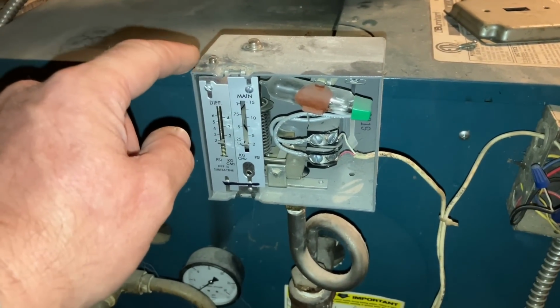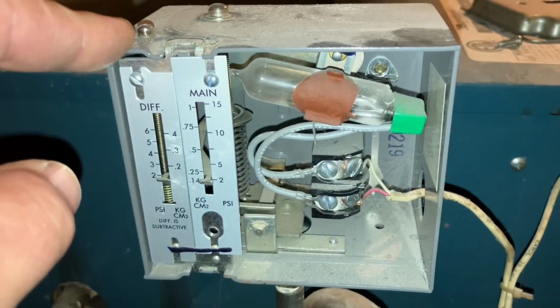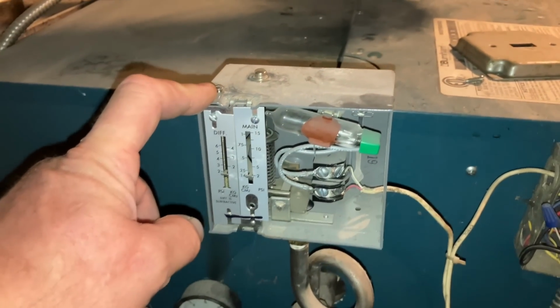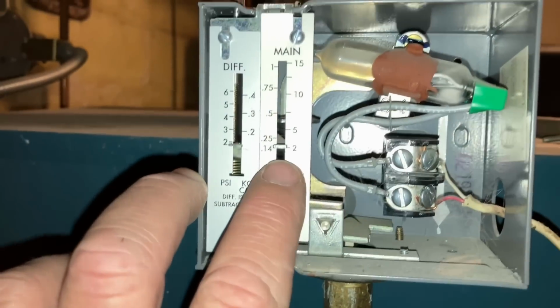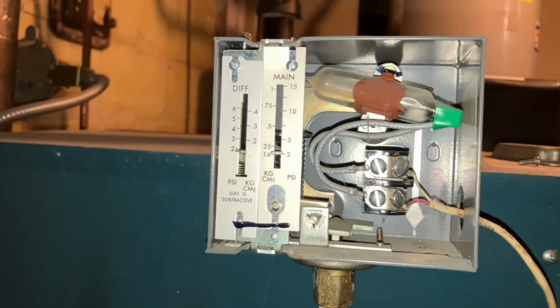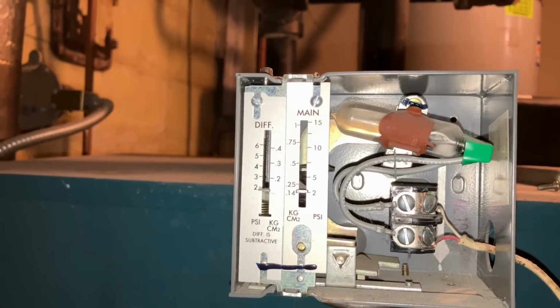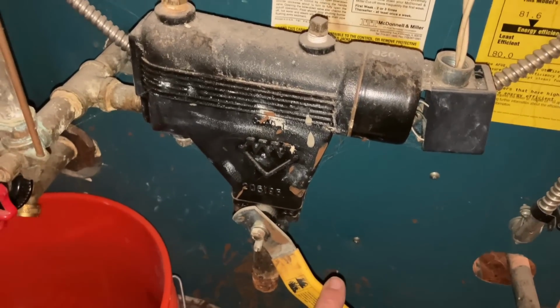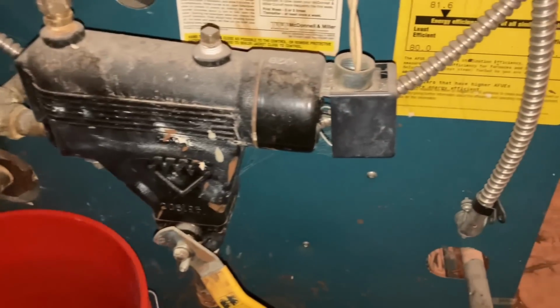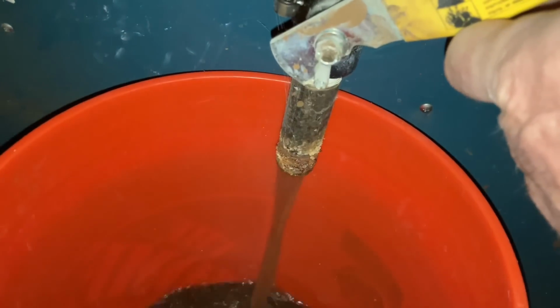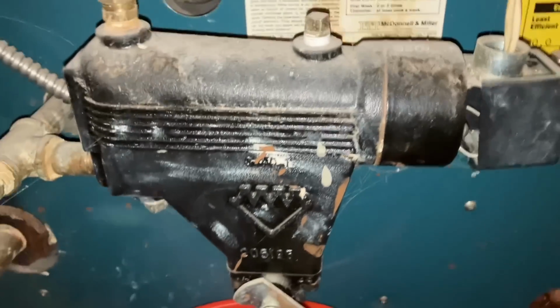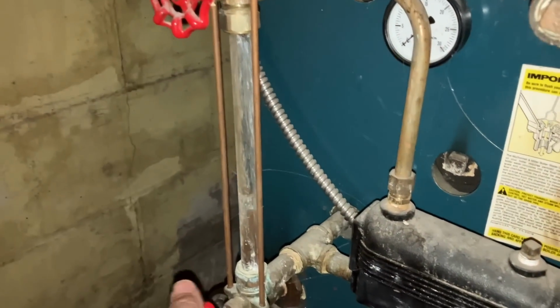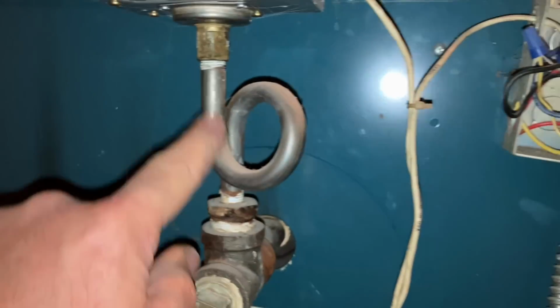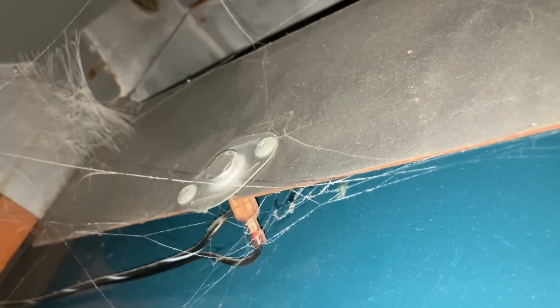That's why you see in an old Honeywell Yo-Yo T87F, you'll see a mercury bulb in there, just like this Honeywell pressure control, which is set to a hair over 2 psi with a differential of maybe a little under 2 psi. Number 67 McDonnell Miller low water cutoff. This is the float style. Let's see what kind of cock we got in there. Not too bad. This nipple's seen better days though. Here is our sight glass, pressure gauge, and pigtail to keep the latent heat off of the pressure control. Back there, where those 2 wires are, that's our rollout switch.